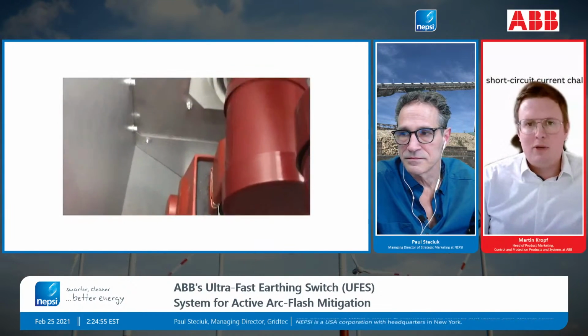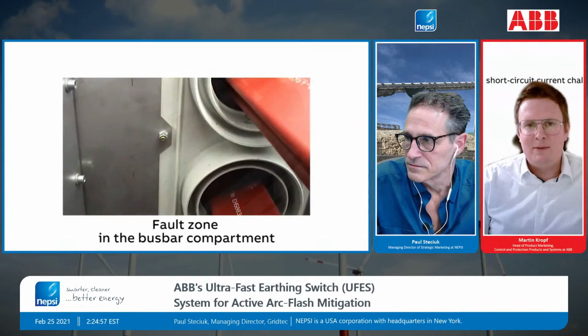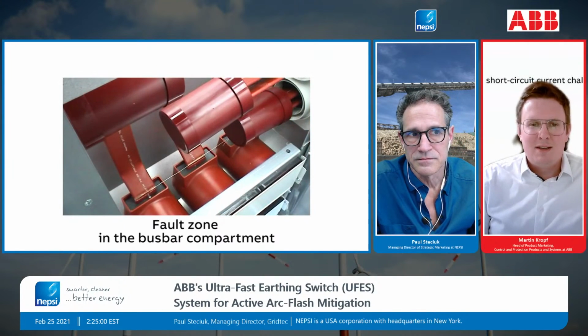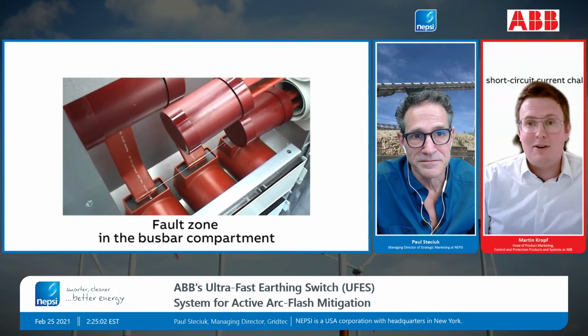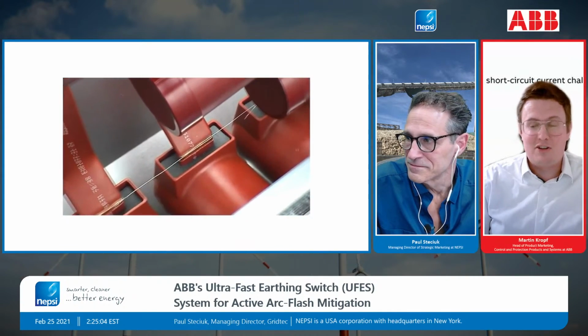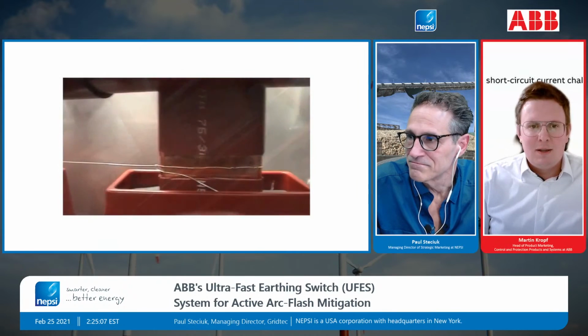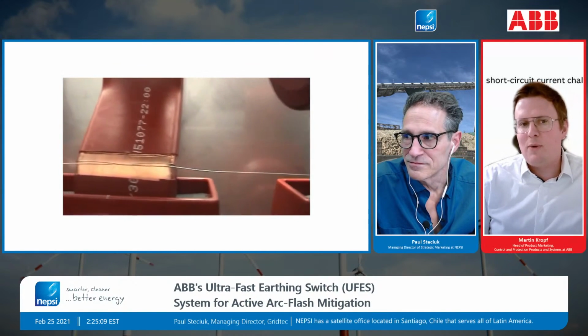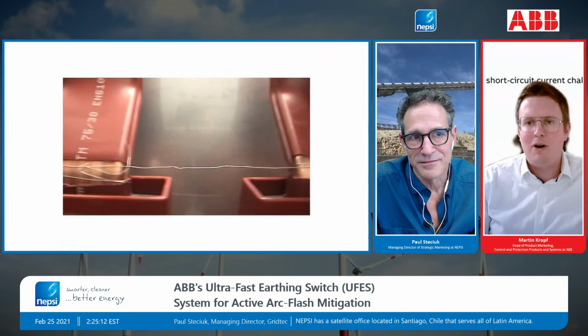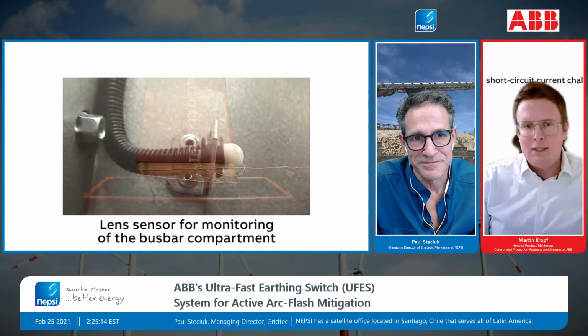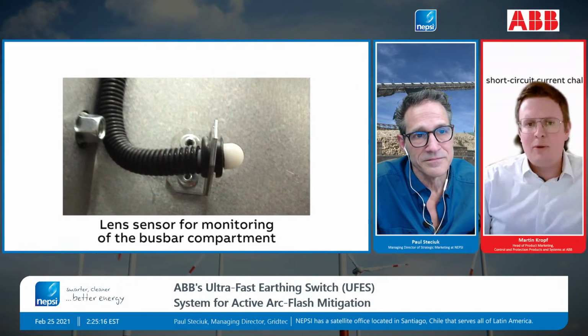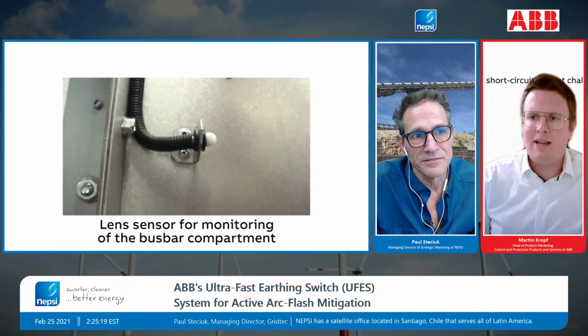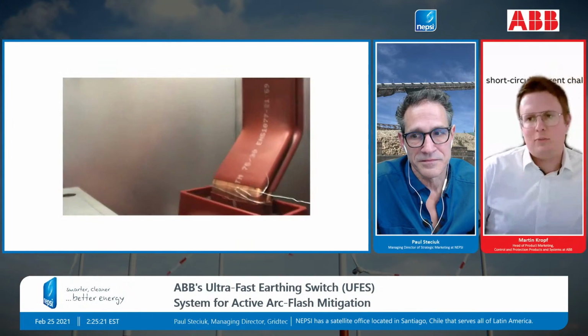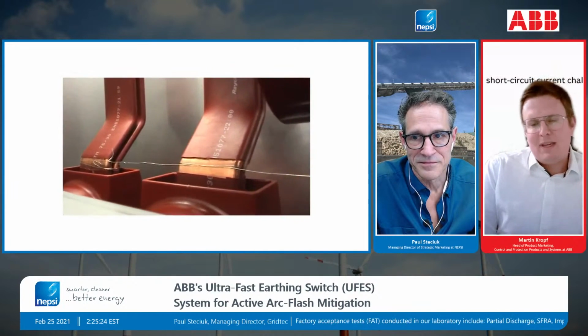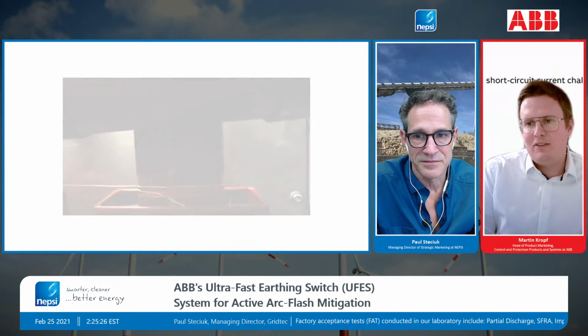On the other side of the switchboard, we have done what we do when we run an internal arc test, where we make an artificial fault. As you see here, we have this initiation wire, so we cut the insulation of the bus bars and made the initiation wire. And then we have the light sensors installed. We normally use in a switchboard 1 light sensor per compartment, so 3 light sensors per panel. So the disaster is ready in the switchboard.